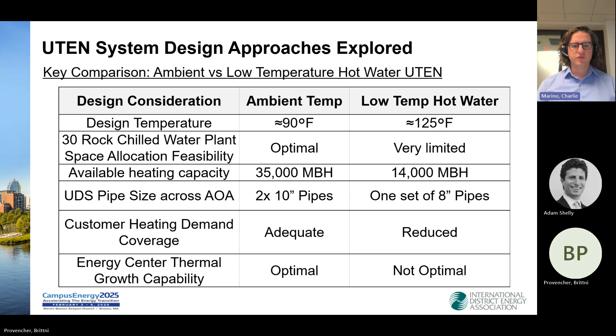If we generated low temp hot water at 125, which was more advantageous for the customer side, we'd be limited on overall capacity, not just for the stage 1 pilot phase but for potential future expansion. We also considered pipe sizes. For this pilot, we sized the customer UDS related to the heat pumps at their sites, and the ambient loop requires two separate pairs, which I'll show in the diagram shortly. There were areas where low temp hot water made more sense based on pipe size and constraints in individual streets.